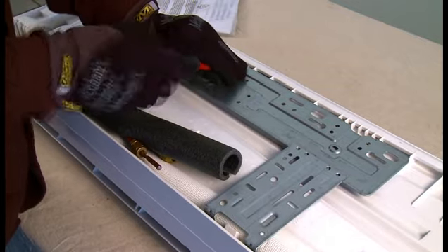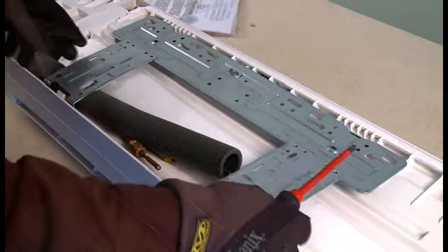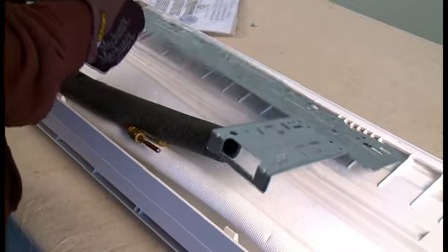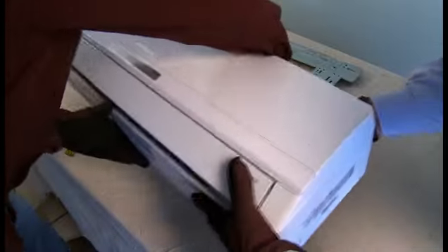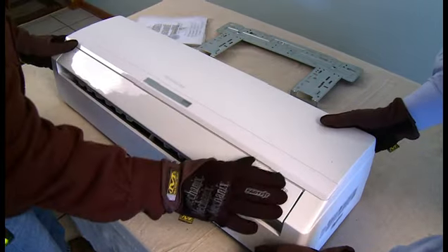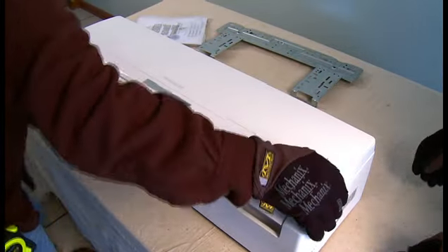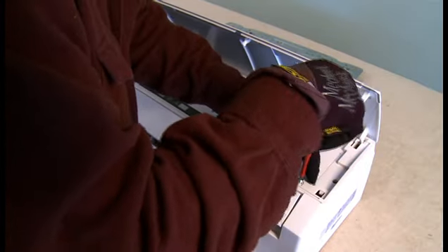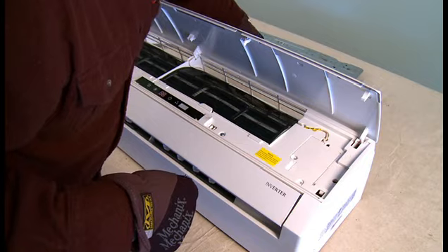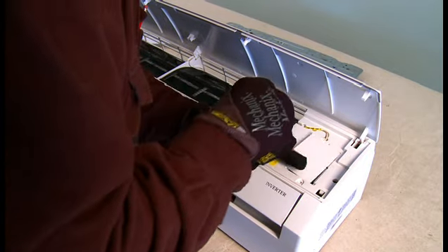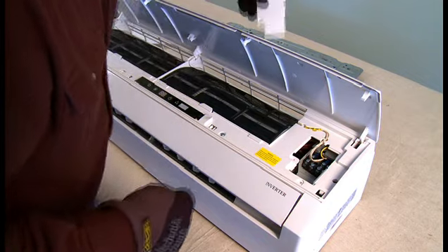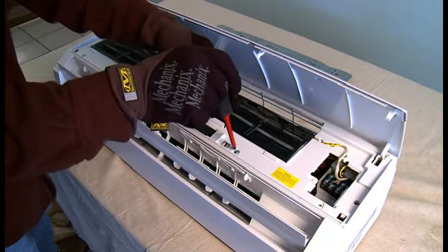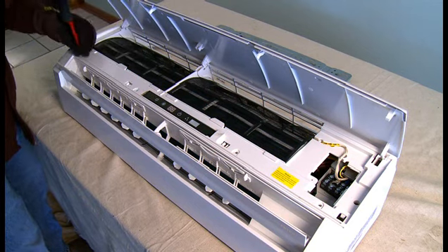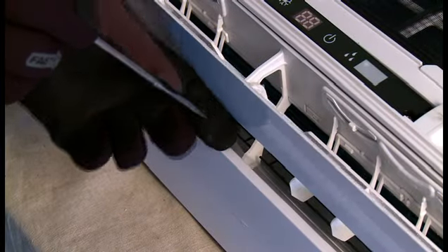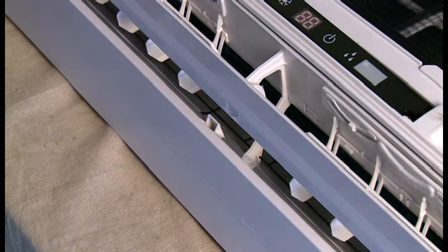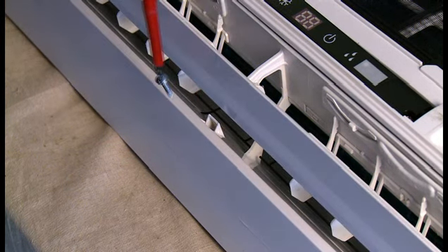Using a number 2 Phillips screwdriver, remove the center screw to release the installation plate from the interior unit's housing. With assistance, turn the interior unit over. Next, open the unit's front panel. Remove the screw that secures the electrical box cover and set the screw aside. Now, remove the electrical box cover. In this step, we'll remove the interior unit's housing. Remove the 3 remaining screws from the top of the unit. Set these screws aside. With a flat blade screwdriver, carefully open the tab to reveal the center screw. Remove this screw and set it aside.